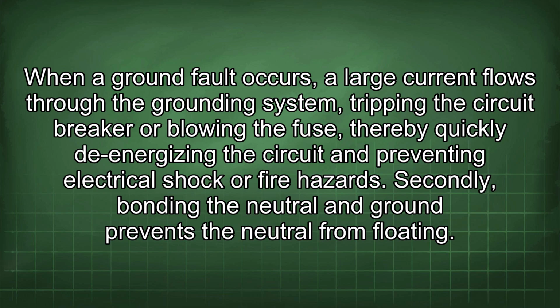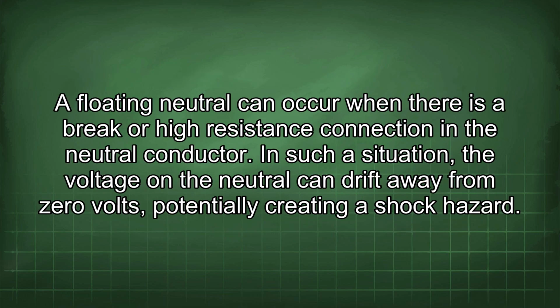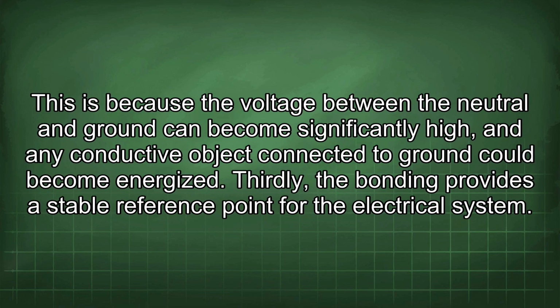Secondly, bonding the neutral and ground prevents the neutral from floating. A floating neutral can occur when there is a break or high resistance connection in the neutral conductor. In such a situation, the voltage on the neutral can drift away from 0 volts, potentially creating a shock hazard. This is because the voltage between the neutral and ground can become significantly high, and any conductive object connected to ground could become energized.